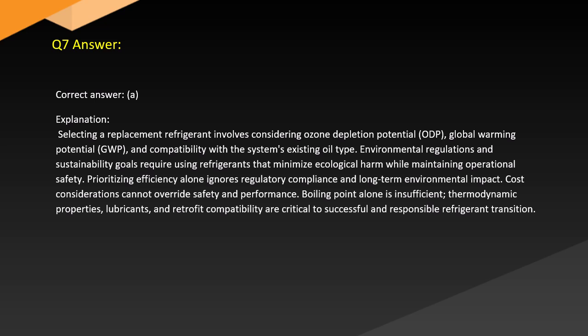Answer. Correct answer: A. Explanation. Selecting a replacement refrigerant involves considering ozone depletion potential, global warming potential and compatibility with the system's existing oil type. Environmental regulations and sustainability goals require using refrigerants that minimize ecological harm while maintaining operational safety. Prioritizing efficiency alone ignores regulatory compliance and long-term environmental impact.